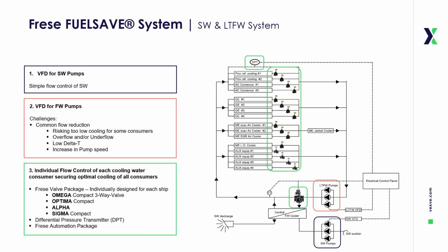The valve package consists of Omega 3-way temperature control valve, Optima compact pressure independent control valves, Alpha and Sigma compact pressure independent balancing valves. The overall automation package is guided by a differential pressure transmitter placed in the loop of the system that meets the highest resistance, the so-called index loop.